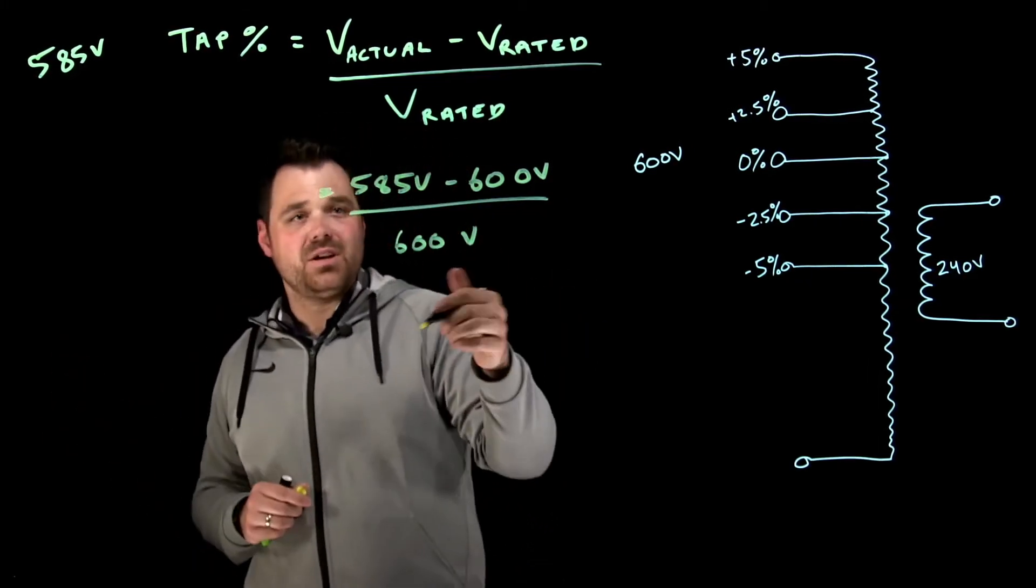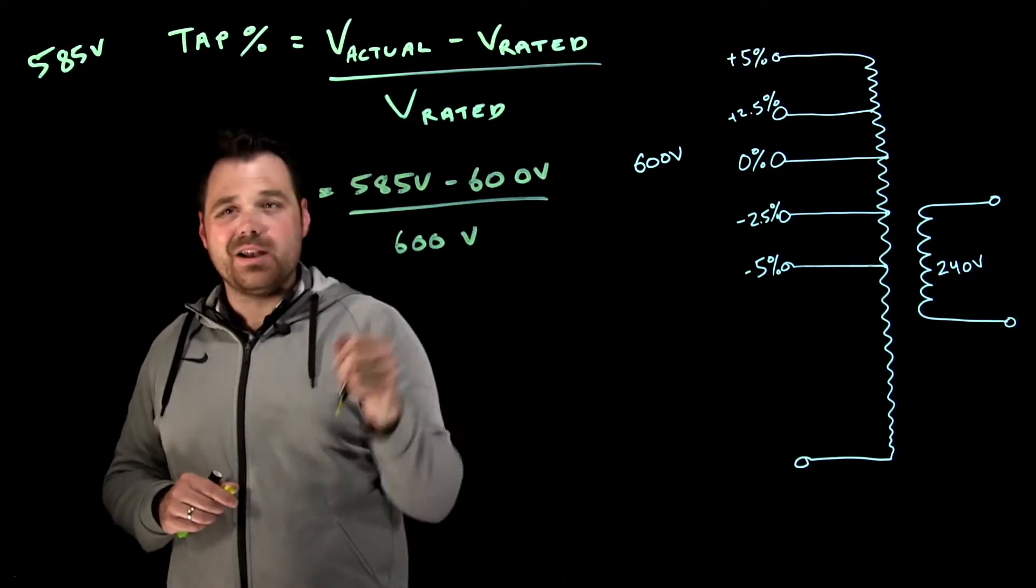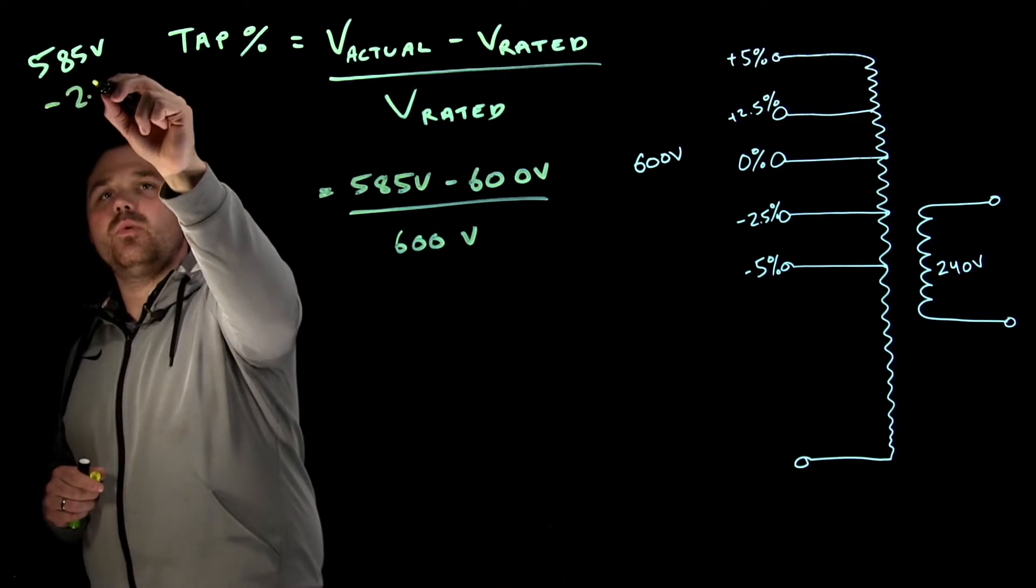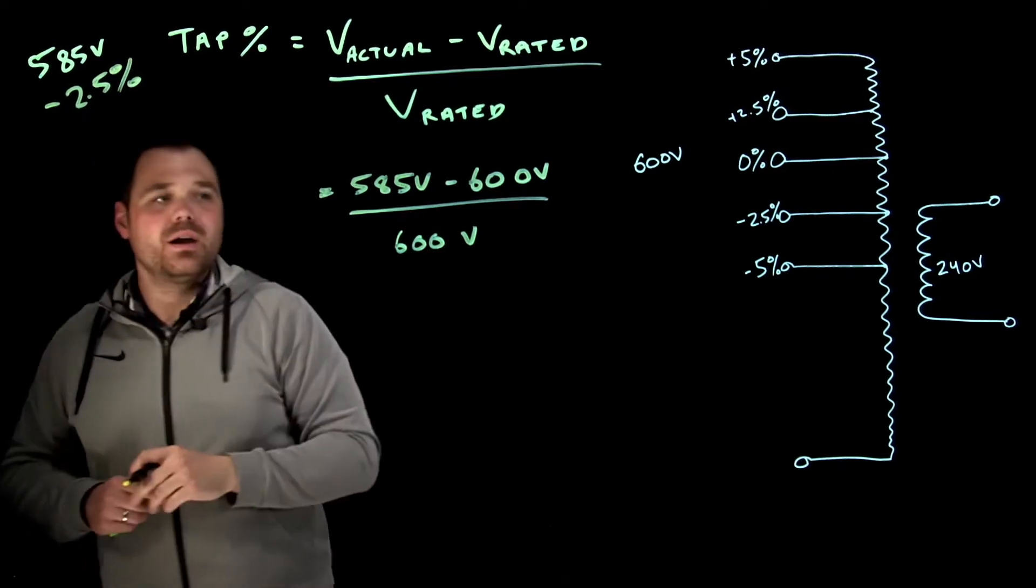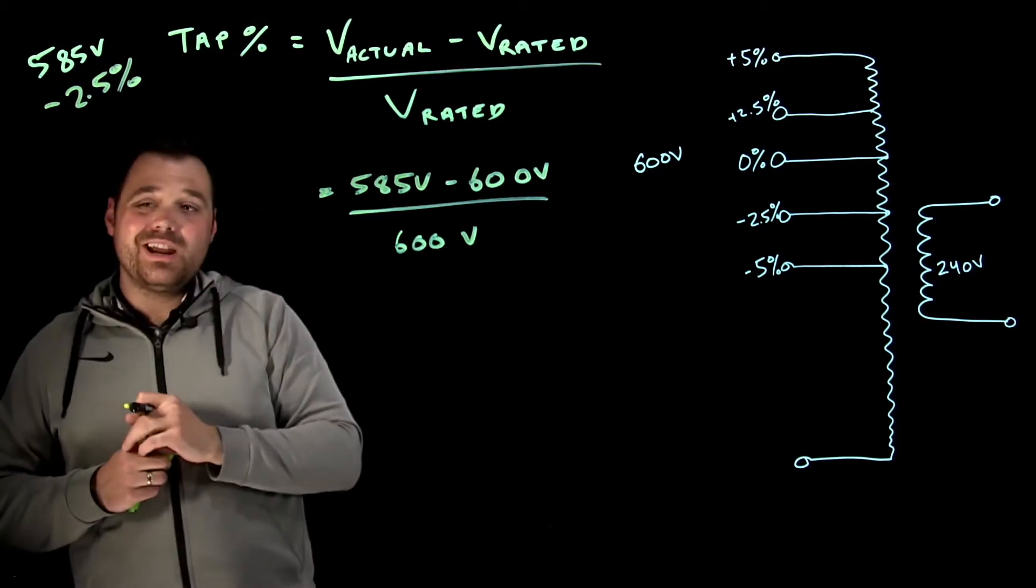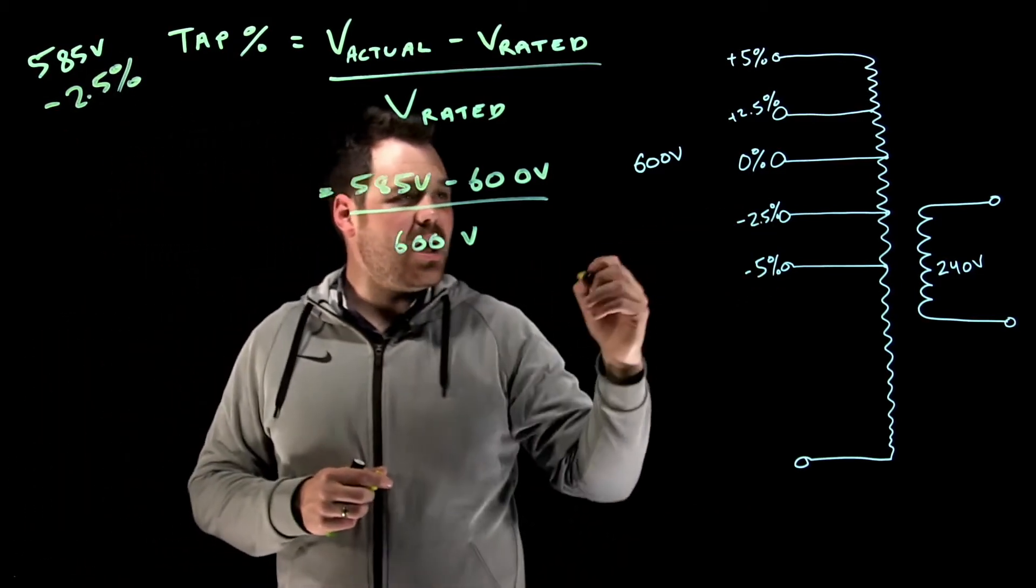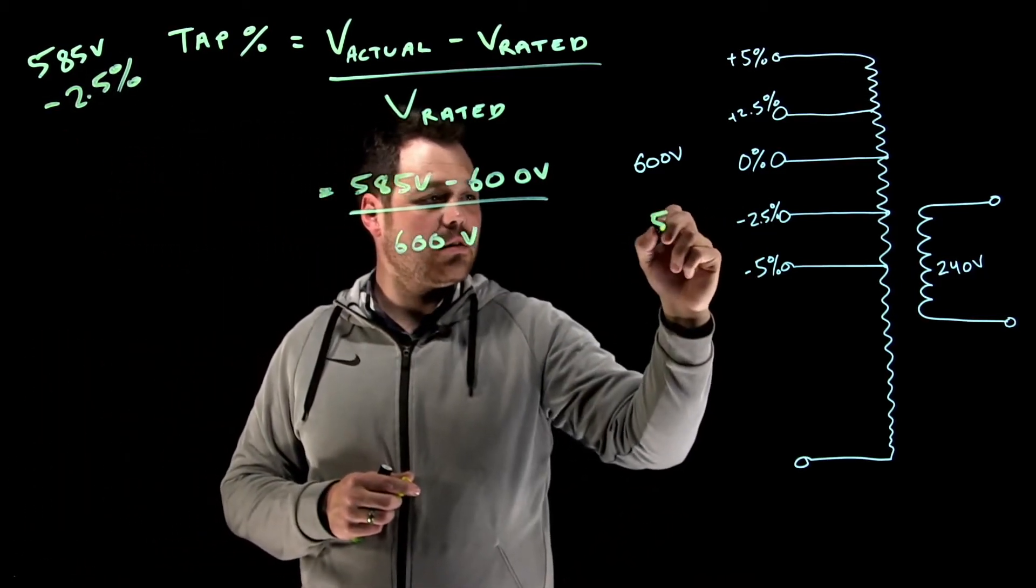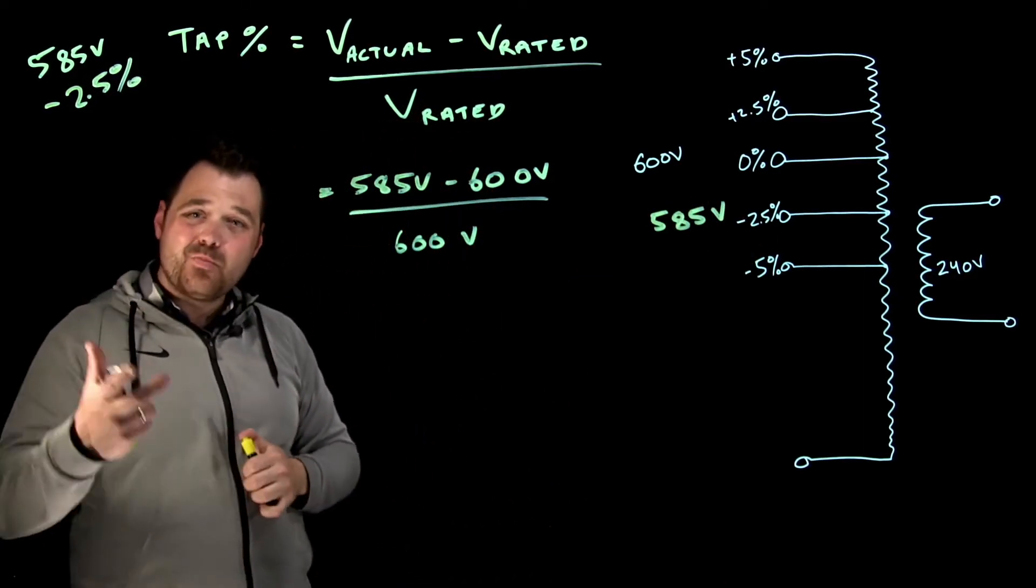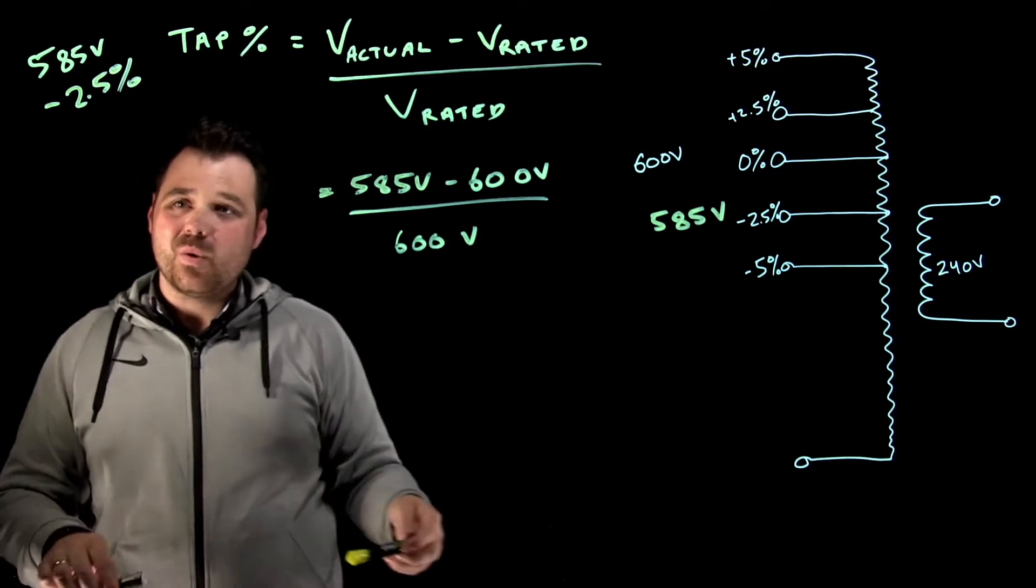Okay, that is going to give me negative 15 divided by 600 gives me a negative 2.5% tap. So if I were to connect my 585 volts up to negative 2.5%, I would get my rated output of 240 volts.